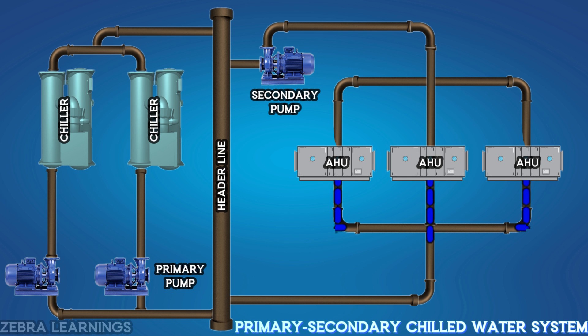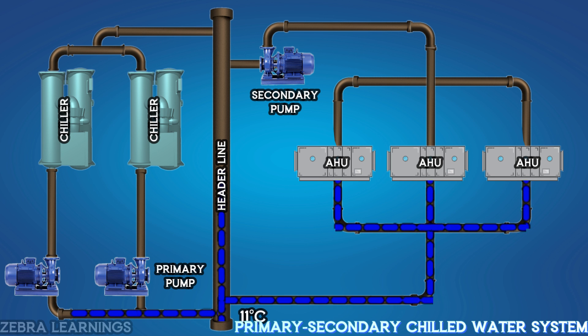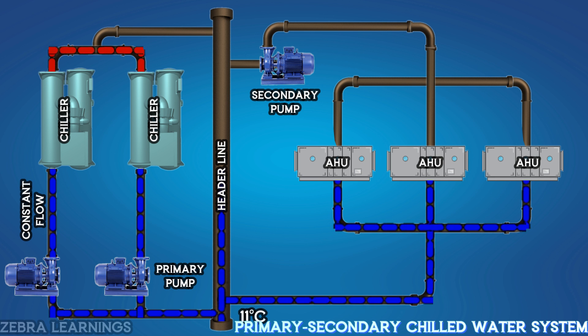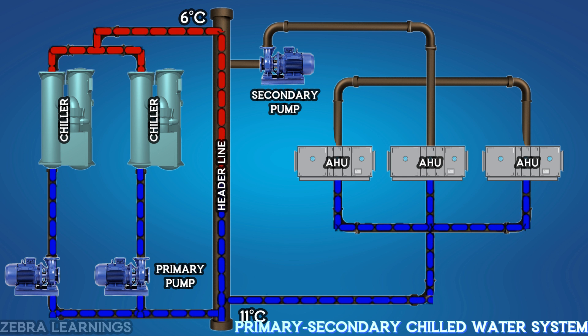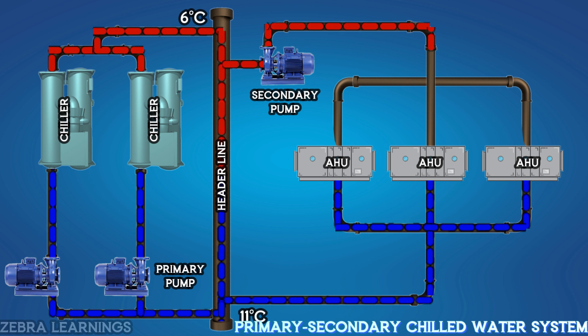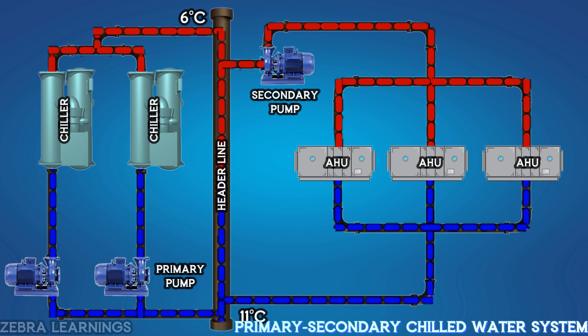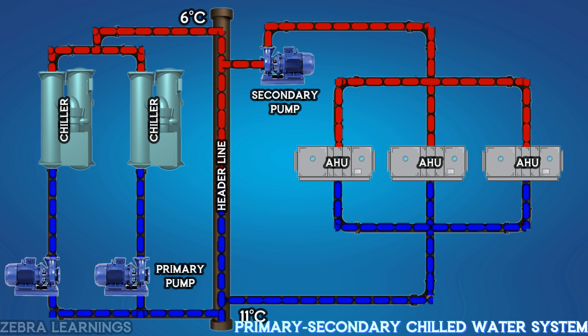Water from the AHU returns to the header line at 11 degrees Celsius. The primary pump sends the water from the header line to the chiller. The primary pump is running at a constant speed so the chiller can get a constant water flow. The chilled water from the chiller leaves at a temperature of 6 degrees Celsius and goes to the header line. The secondary pump sends the chilled water from the header line to the AHU in the building. The return water from the AHU is then sent back to the chiller by the primary pump, and this process continues continuously.